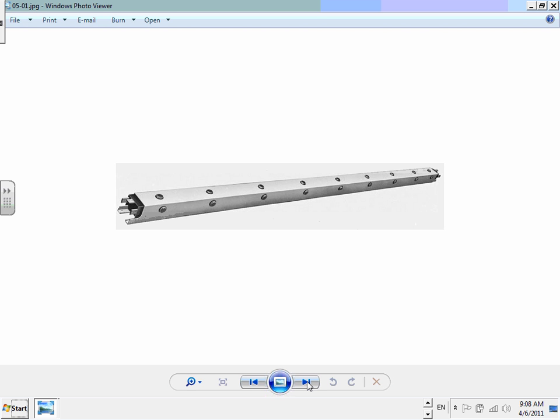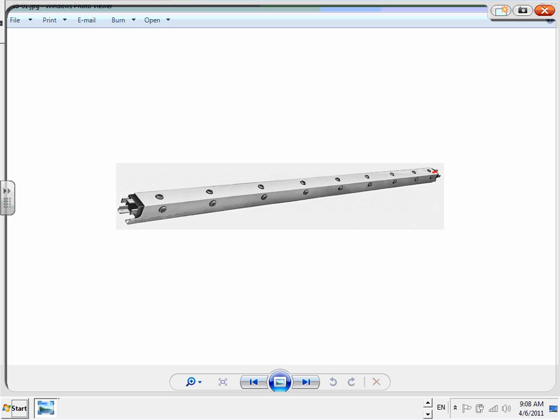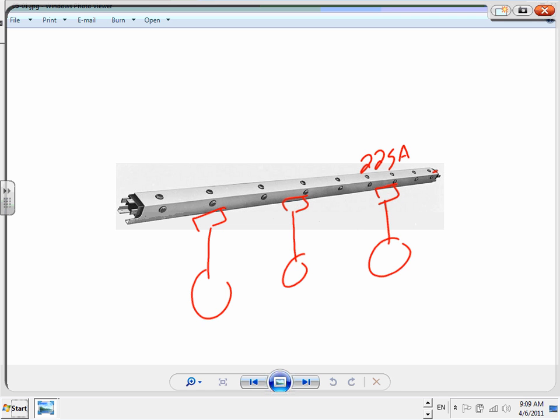In our project, guys, we have three plug-in busways. Look at them. If you guys remember, we reviewed them. 225 amp is a good size for them. Good starting size. One thing I want to mention, guys: this is 225 amp, and the equipment that's connected to it, the load, say suppose the load was 94 amps. I calculated the load on this one and it's 94 amps. The smallest that I can go to is 225 amps.